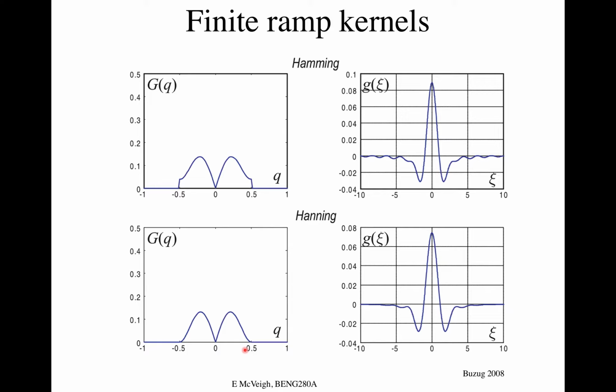And if you were looking for a big blob, then the Hanning's fine. And it turns out that radiologists will ask you to set these filters differently if they don't like the feel of the picture. Oftentimes radiologists, when they're looking for things, their comfort at looking at the picture is important. And if the picture looks really hashy and they don't like it and they're not confident in it, then it's better to smooth it, and they'll tell you that.